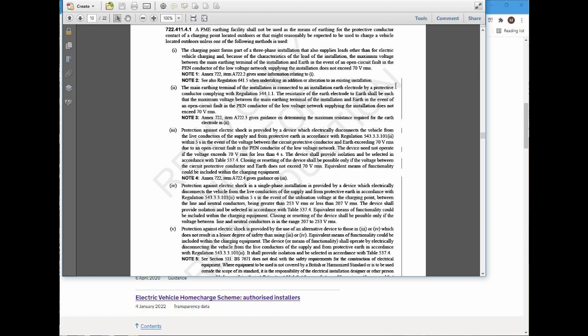There should be a means of detecting an open PEN fault or broken PEN fault. Most charging units should have one of these inside, or at the very least you should have a third-party one put in place to detect this. Like I mentioned, no system is absolutely perfect yet. They've not developed a perfect way of detecting this.